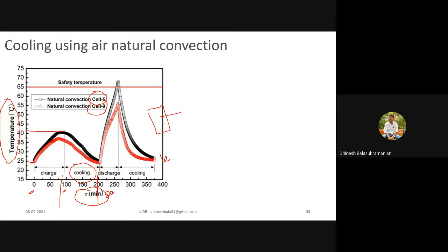It is evident with this particular graph also. Cell number 5 results in a very high temperature of around, let us assume it is 68 degrees Celsius, whereas cell number 9 results in only 55 degrees Celsius. We are aware from the previous slides that our desired temperature range is 15 to 35, and at any point of time we should not exceed the safety limit of 60 degrees Celsius for the lithium ion battery. But for this case, they have considered the safety limit as 65. For this discharge cycle, the temperature of the battery has risen above 65 degrees Celsius, displaying a temperature of around 68 degrees Celsius.